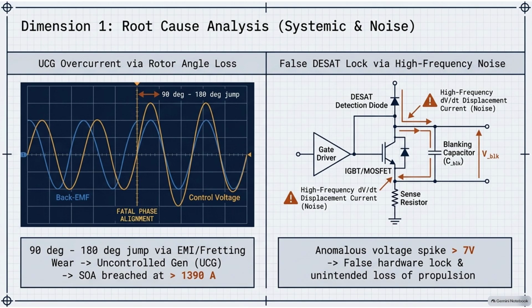When that angle jumps 180 degrees, the software thinks it's applying driving torque. But the electrical vectors are now entirely out of phase. They align perfectly with the motor's natural back electromotive force. Oh, man. So the motor instantly transitions into an uncontrolled generator. And it just blasts all that kinetic energy backward as electrical current. The data here shows demagnetization currents exceeding 1,390 amps surging straight back into the system. It violently breaches the safe operating area of the power transistors. It's a complete structural failure, and it's all driven by a hallucination in the sensor data.